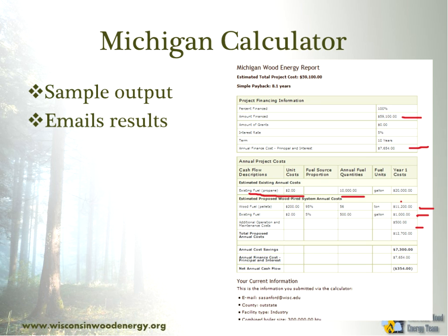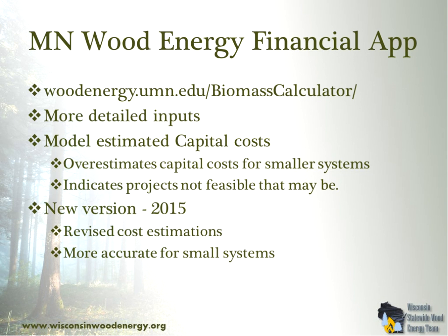Last week we talked that sometimes going less than that is optimal. The other thing it does is it looks at the wood boiler is sized at half the size of your existing boiler because a lot of boilers are oversized to begin with. And what it's trying to do there is not to get it too big so it runs more continuously to supply heat.